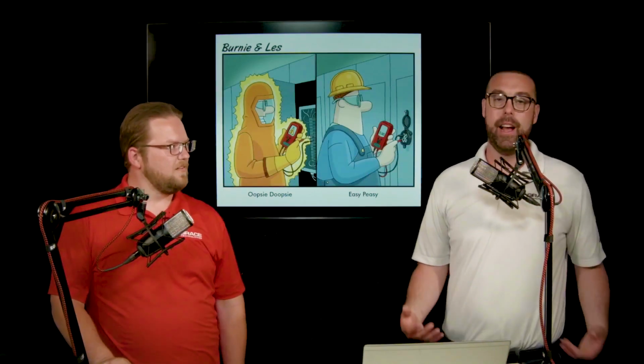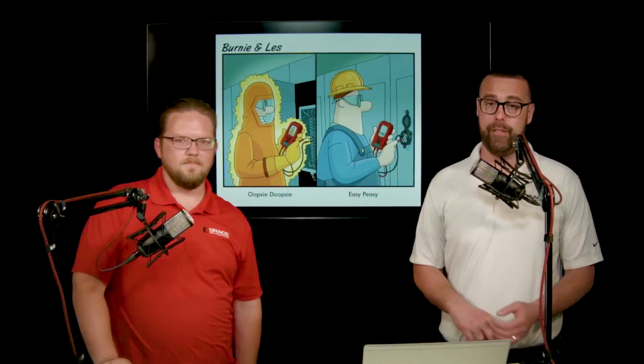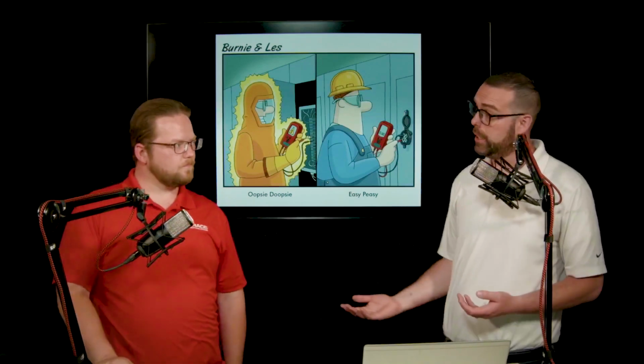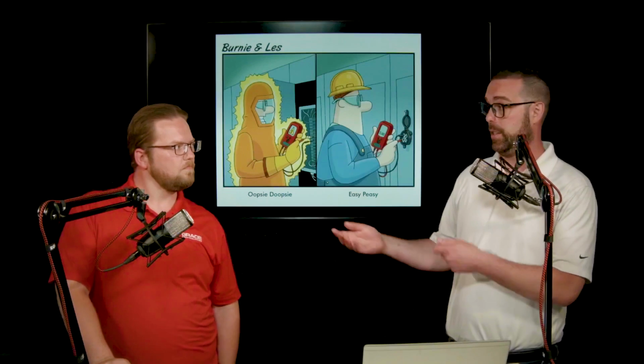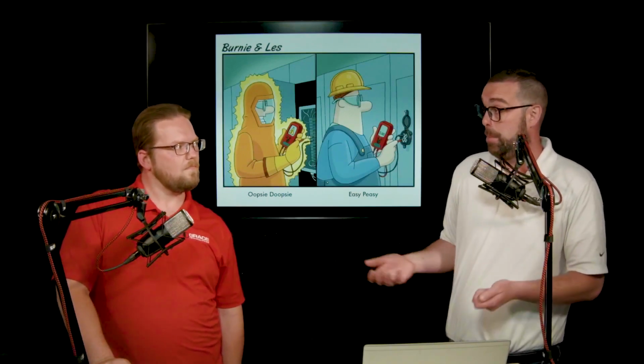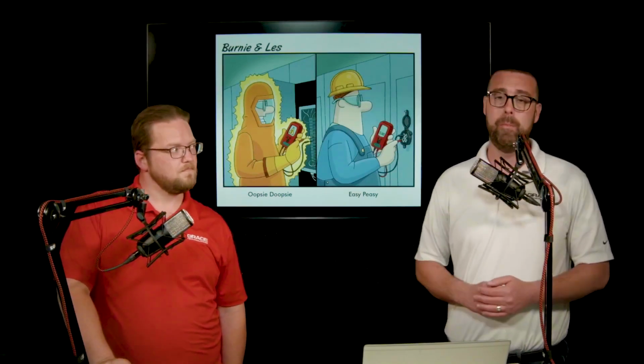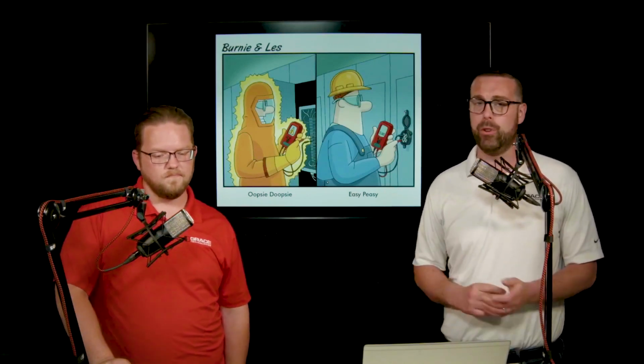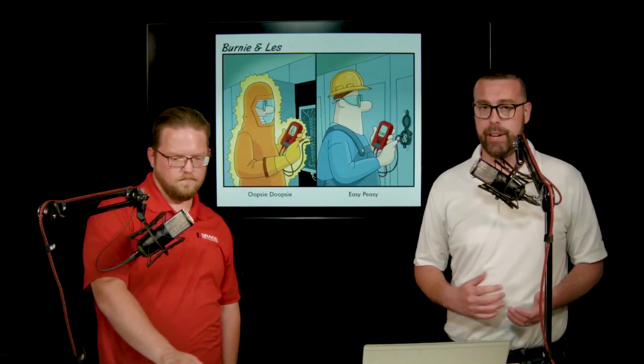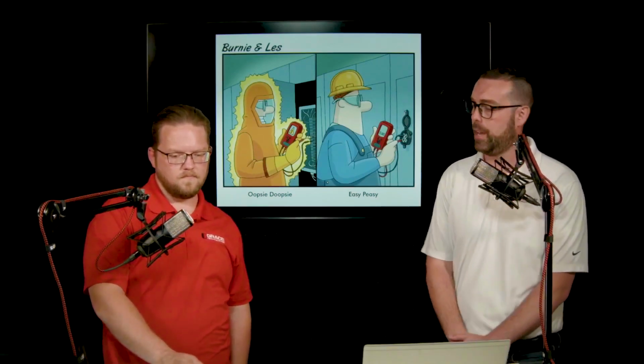I think there's definitely a level of experience and comfortability at play, and that's where performing that contact test could potentially create an arc incident. So that's where we tailor a lot of our permanent electrical safety devices toward lower voltage applications, generally 1,000 volts and less. 480 is very common, and we also see some single phase applications as well.